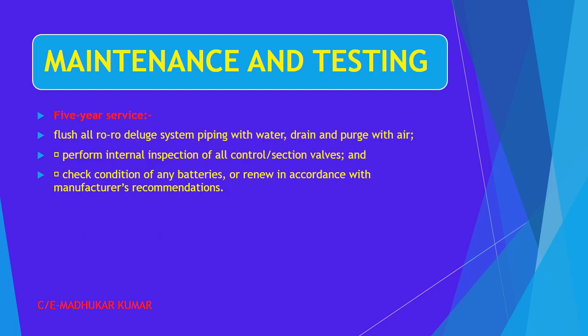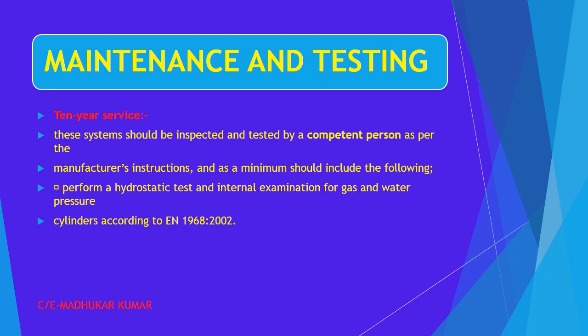1516. Now 5-year service, including the annual service, flush all the Ro-Ro deluge system piping with the water. Suppose in the Ro-Ro system we have the pipelines and all, so the drains, the pipelines and all these things have to be checked, and they have to be purged with the air. Perform internal inspection of all control section valves. Okay, check condition of any batteries or renew in accordance with the manufacturer's recommendation. Suppose for the control panel or anywhere any batteries are there, the 5-yearly period it must be renewed.